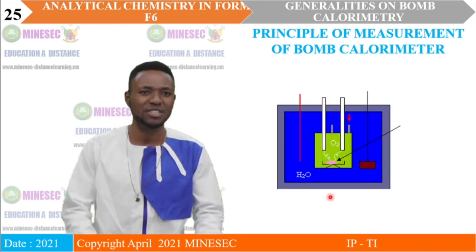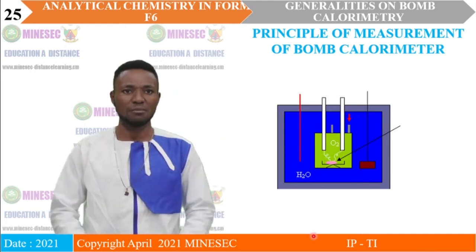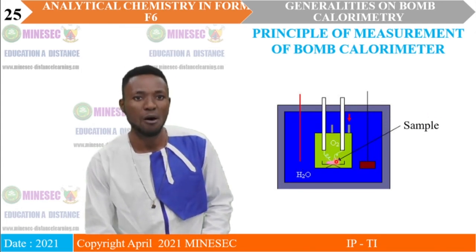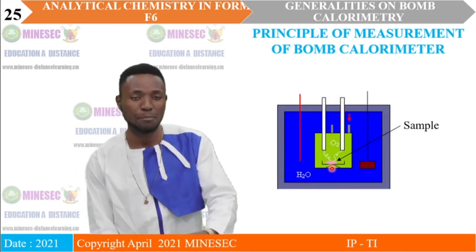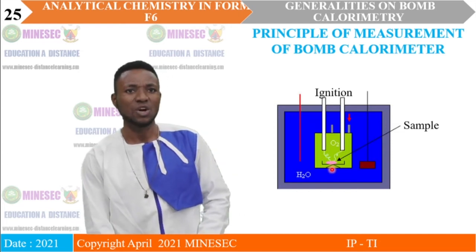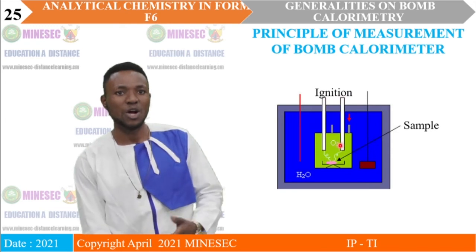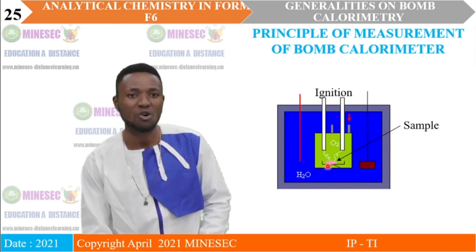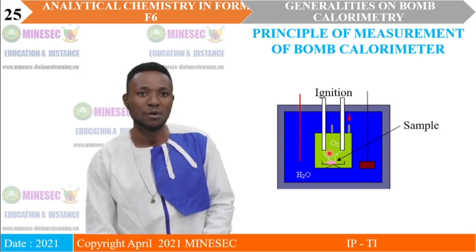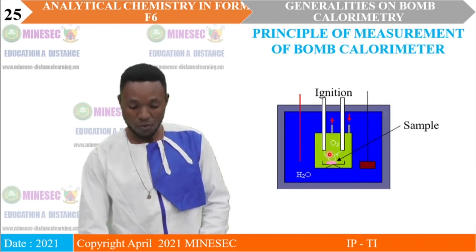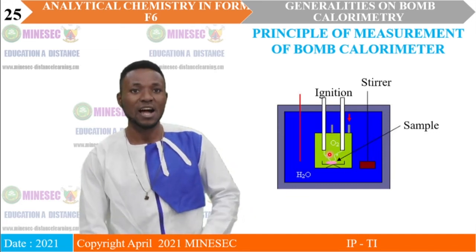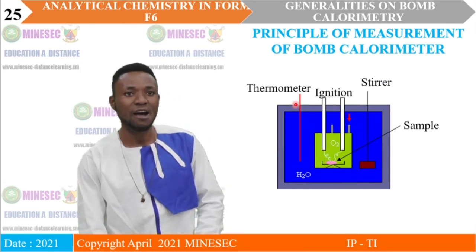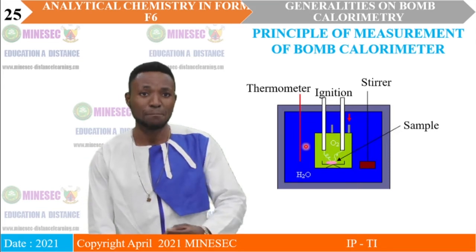Let's now look at the principle of measurement of the bomb calorimeter. First, we place our sample in the bomb on the sample carrier. After that, we turn on the ignition, which connects the two electrodes and causes combustion of the sample. Heat is generated and evenly distributed in the water through the stirrer, and the thermometer is used to read the temperature of the water.